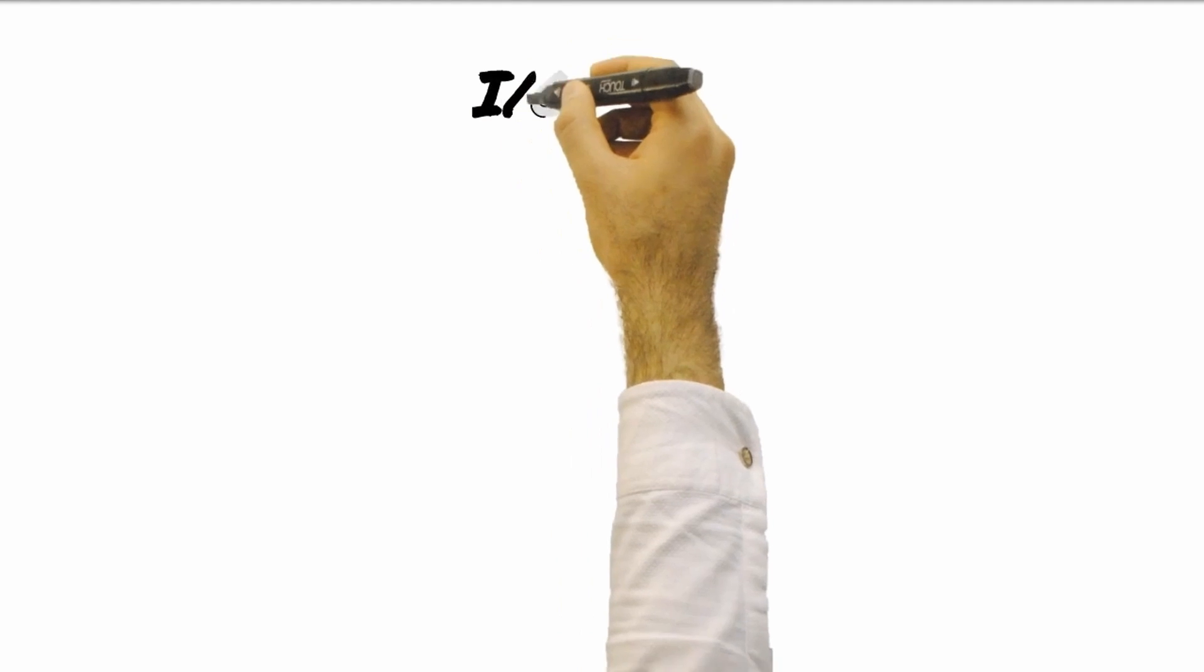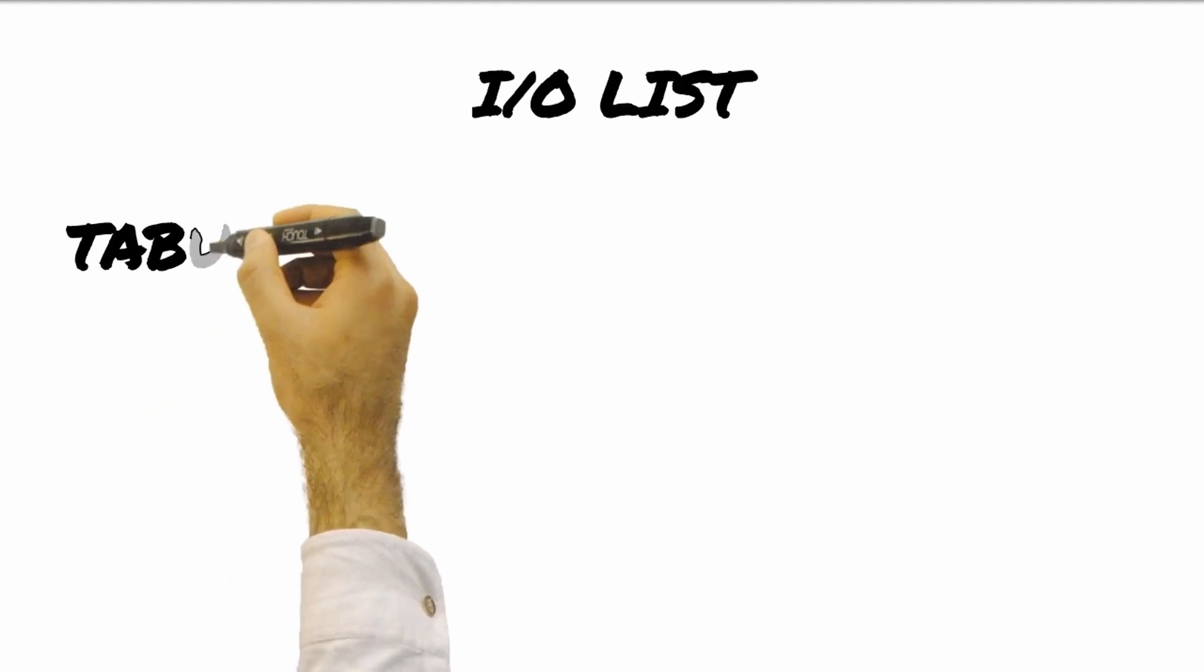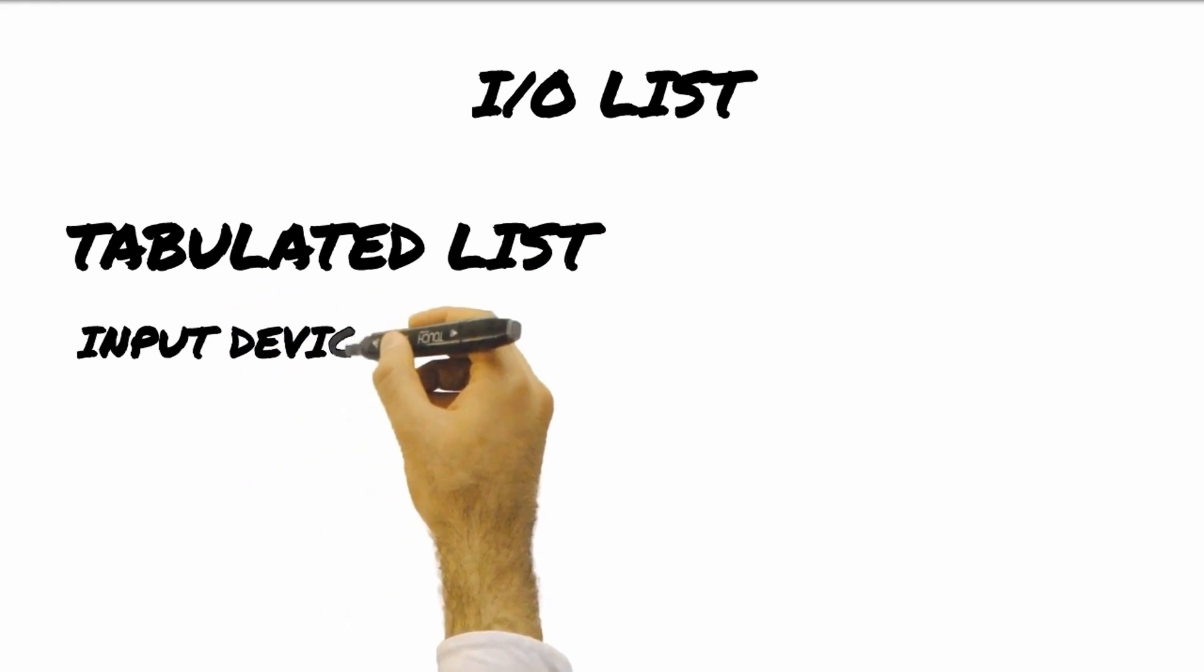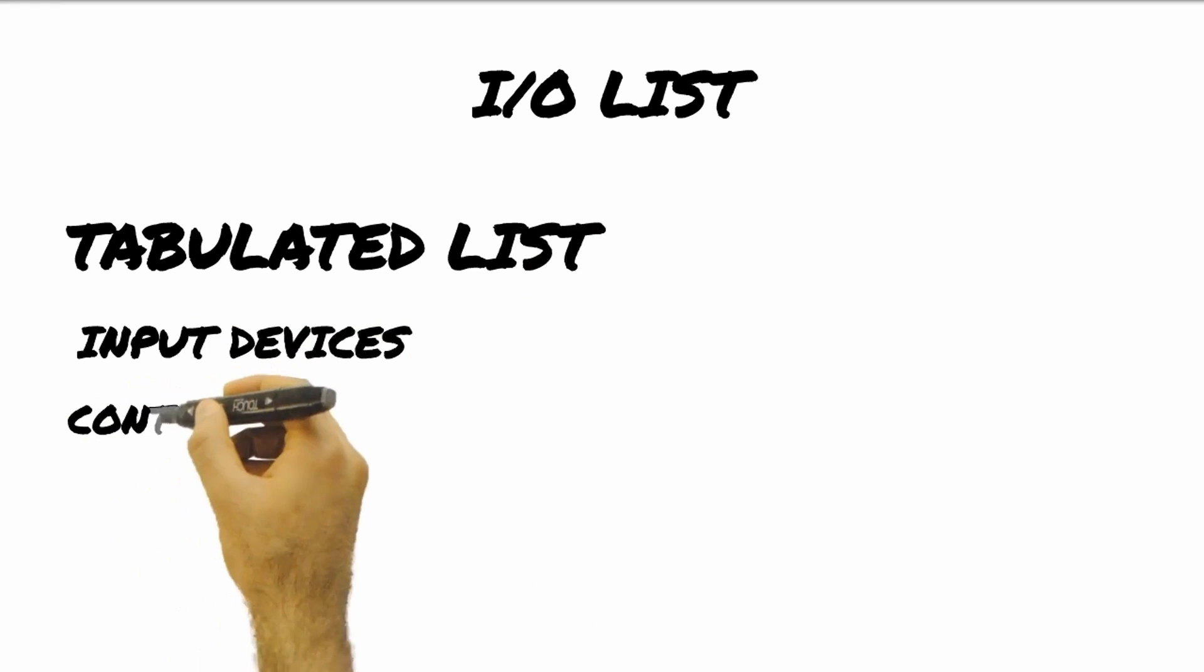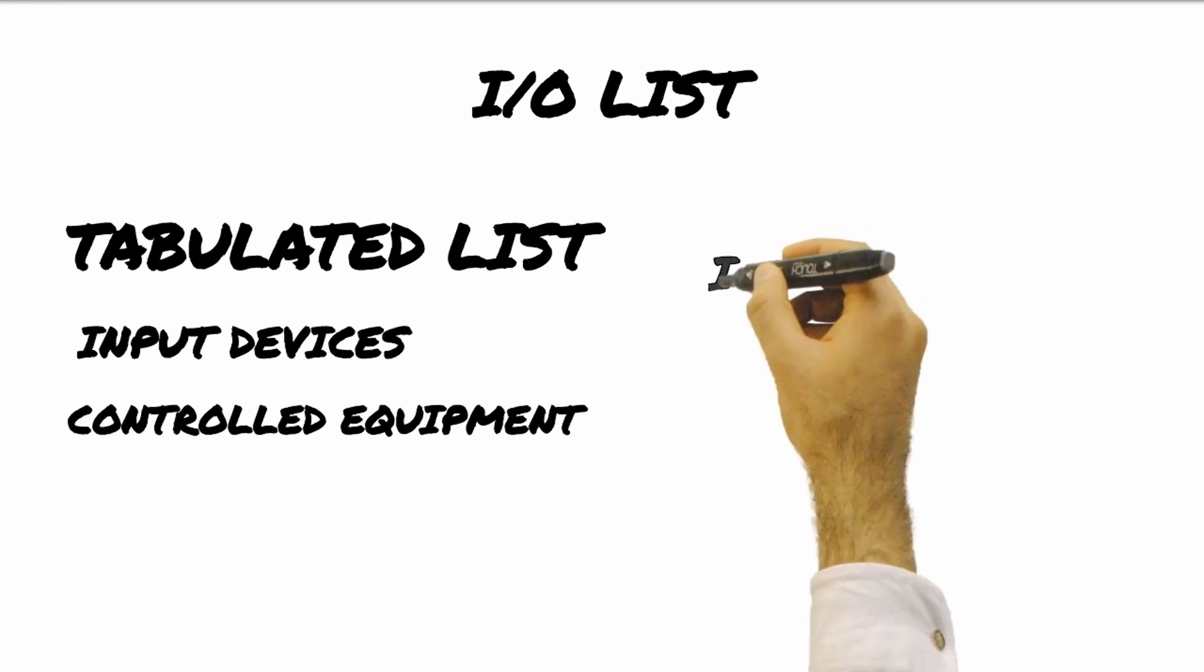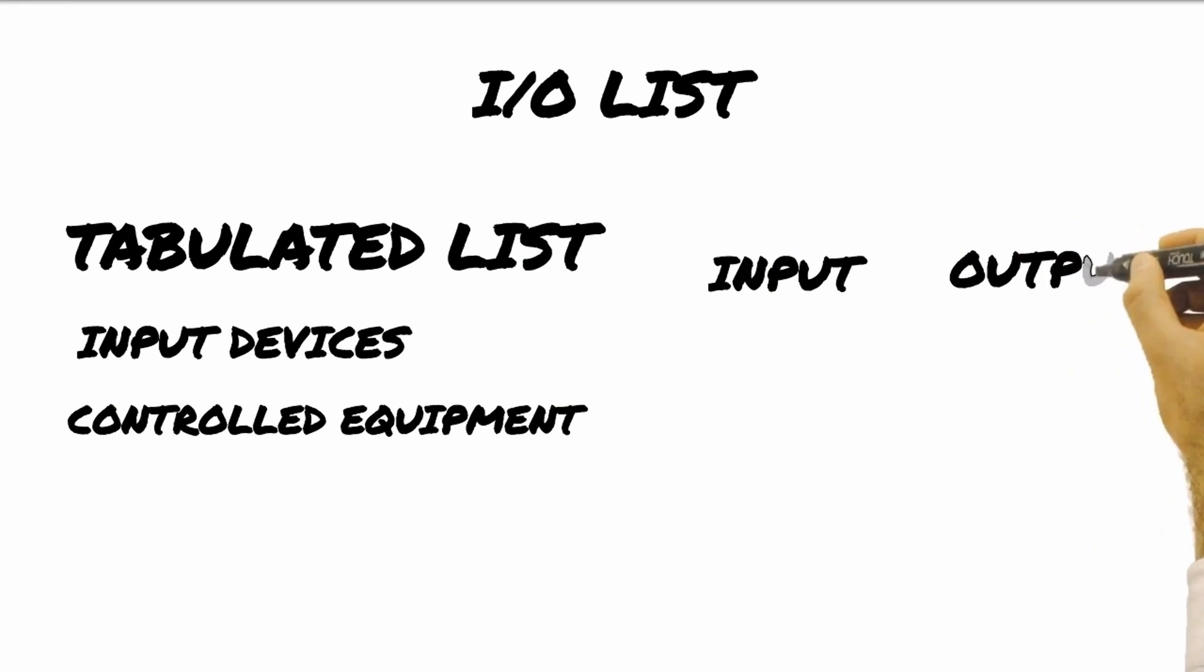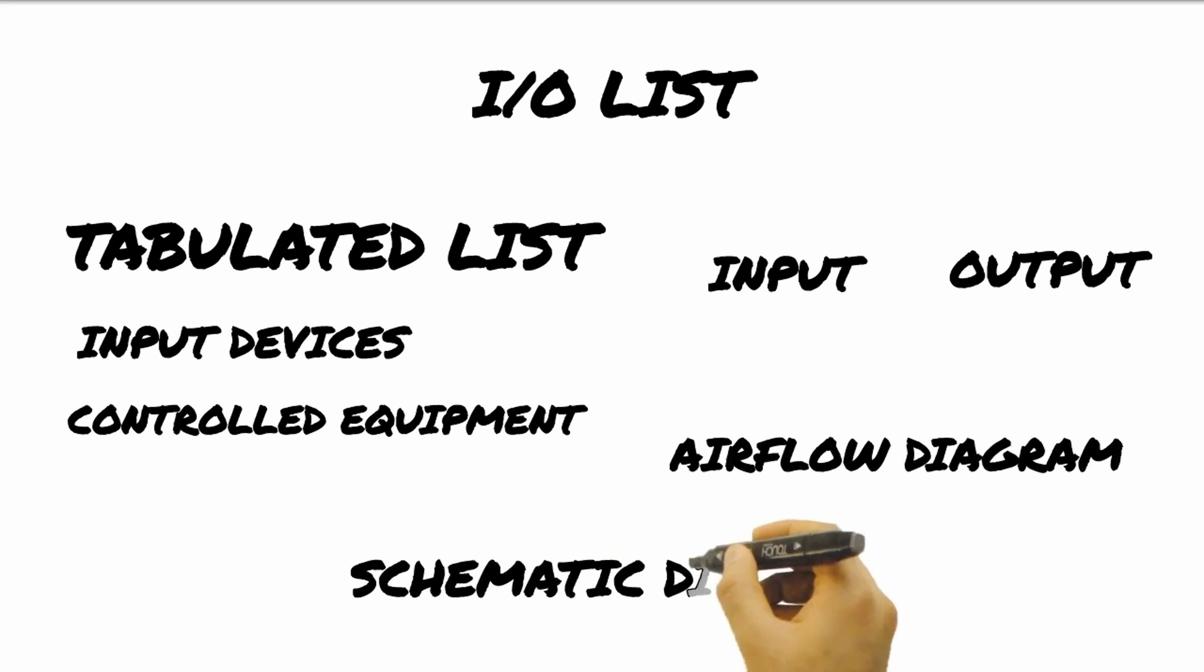Another important document necessary in order to design the DDC for HVAC system is the I/O list. This is a tabulated list of all the input devices such as the sensors and all the control equipment. It also shows the type of input and output signals going in and coming out of the controller and the quantities of each type of signal. The sequence of operation and the I/O list are important in addition to the airflow diagram and schematic diagram for the control system.